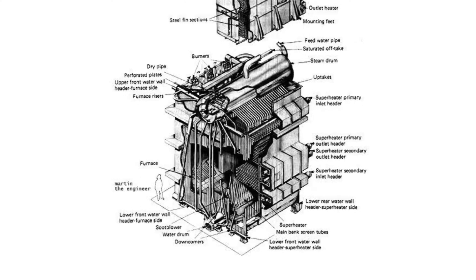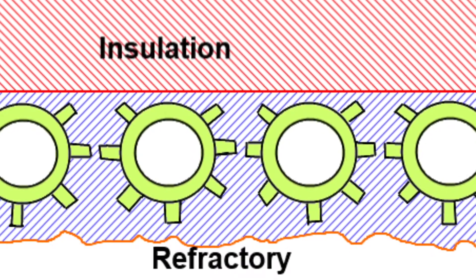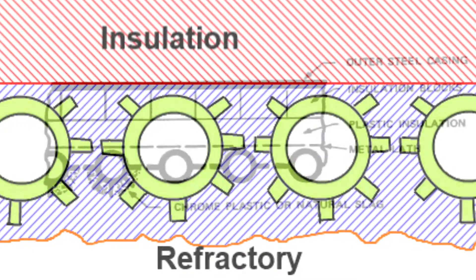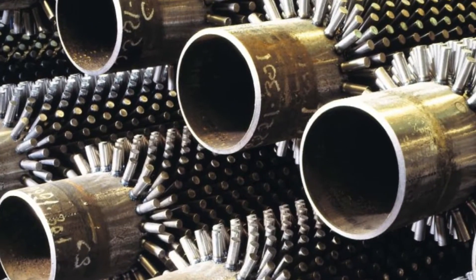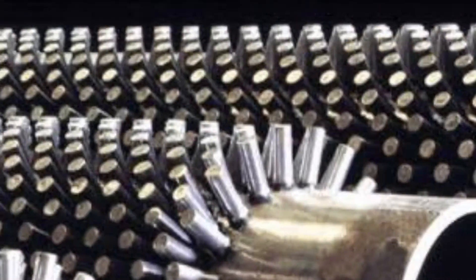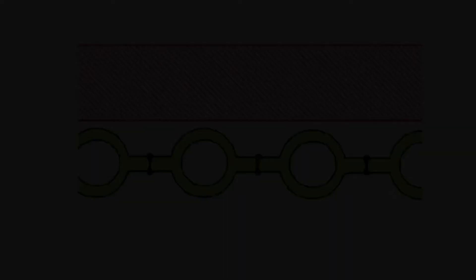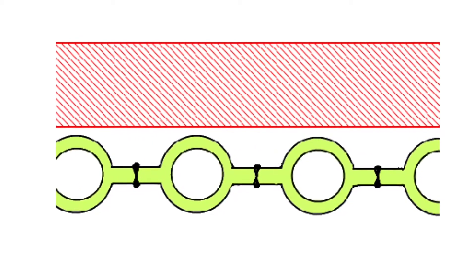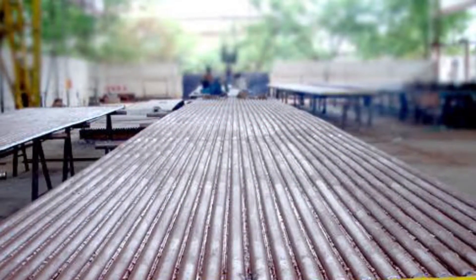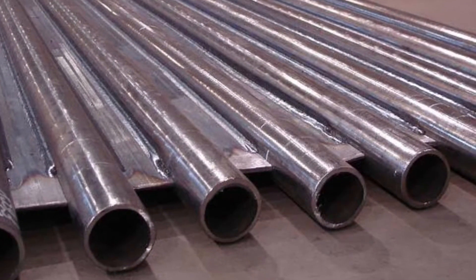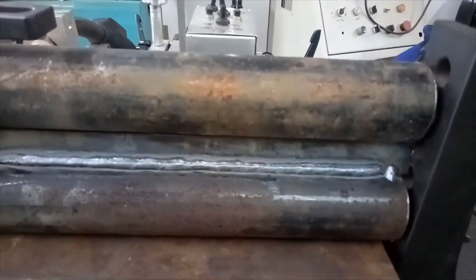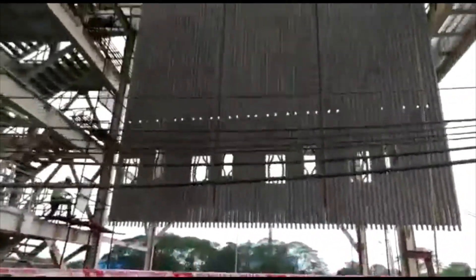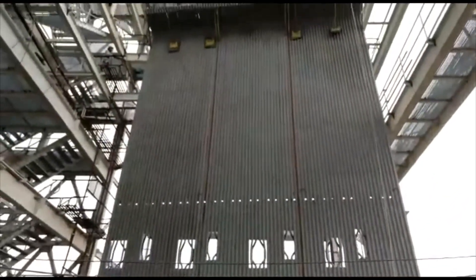Since the 1920s, boiler designs continued to grow in both size and capacity. In the late 1920s and early 1930s, flat studded tube and loose tube wall construction appeared, increasing heat absorption so that boilers of those days could receive the highest heat generated from coal combustion. A major change in water tube boiler wall design occurred in the late 1950s and early 1960s: water tube boiler walls made from long steel tubes arranged in a row and welded to each other with steel membrane bars between every tube. This design made fabrication much easier, with wall panels built at the workshop and then assembled on site, making the process more practical, time-saving, and cost-effective.